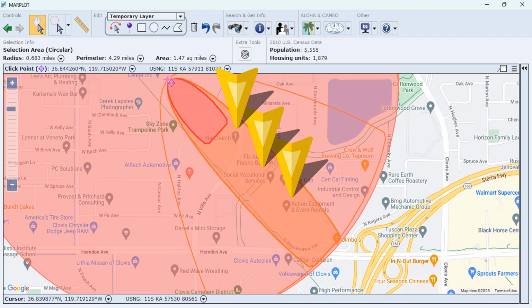In addition, you're also required to identify public receptors that are located within that threat zone. Public receptors include off-site residences, institutions such as schools, child care centers, prisons, and hospitals. It also includes industrial, commercial, and office buildings, parks, or recreational areas that could be occupied by the public, where they may be exposed to concentrations of toxic chemicals, radiant heat, overpressure, just as a result of an accidental release from your facility. And basically, off-site means areas beyond your property boundary where the public has routine and unrestricted access during or outside of business hours.